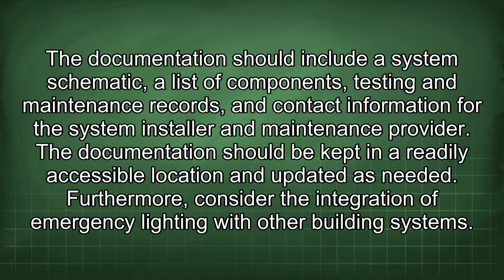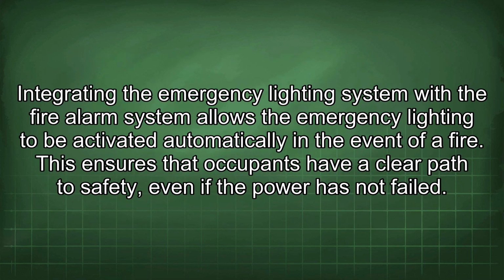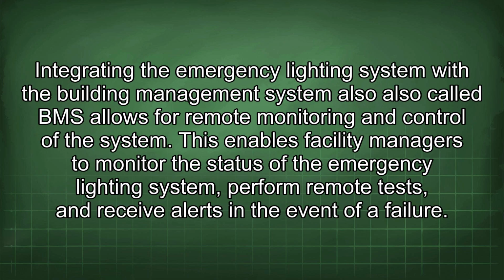Furthermore, consider the integration of emergency lighting with other building systems. Integrating the emergency lighting system with the fire alarm system allows the emergency lighting to be activated automatically in the event of a fire. This ensures that occupants have a clear path to safety, even if the power has not failed. Integrating the emergency lighting system with the building management system, also called BMS, allows for remote monitoring and control of the system. This enables facility managers to monitor the status of the emergency lighting system, perform remote tests, and receive alerts in the event of a failure.